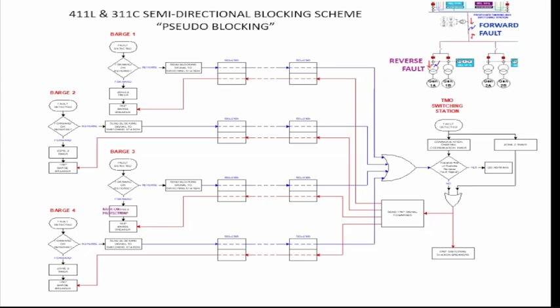It's similar to zone selective interlocking, if you are familiar with it. If the bus is faulted, the protection will act as instantaneous or high speed. If the fault passes through a breaker, or you need to coordinate at the downstream, it will send directional blocking. So there's a connection or communication from the downstream breaker to the upstream, sending a blocking scheme that makes it act as time-delayed protection. We call this the zone 2 blocking scheme.